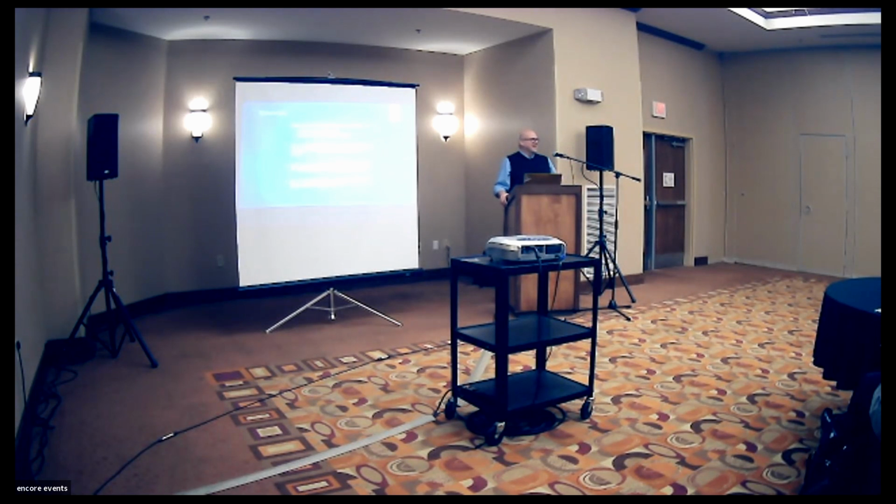There we go. How does the algorithm work if the EPAP's not appropriate? It's still going to try, but you're going to see it probably pressure limiting itself, because the airway is going to be closed and the pressure support's still trying to push, and it will probably start pressure limiting itself there. Meaning it would hit the max. It would hit the max, yes. So it's still going to try, but it's putting it in a tough spot.